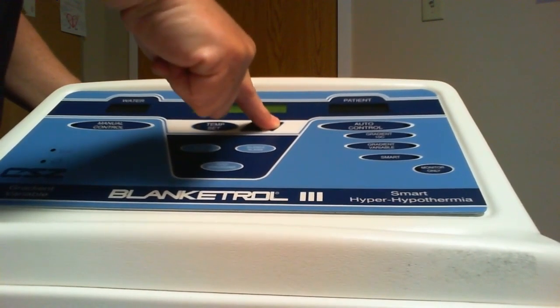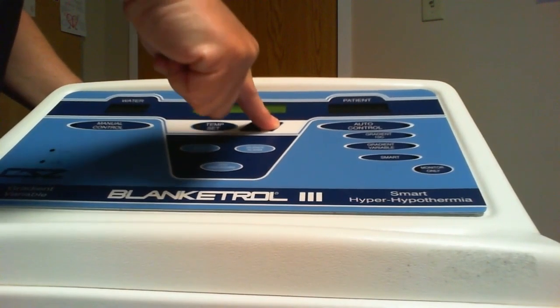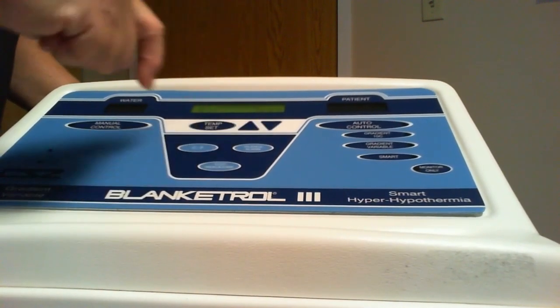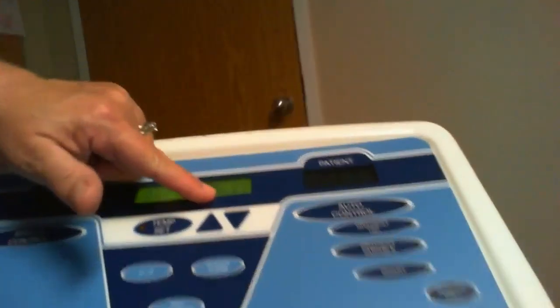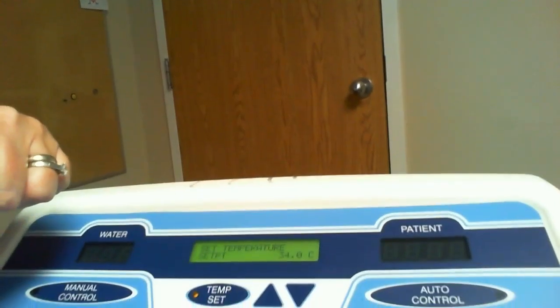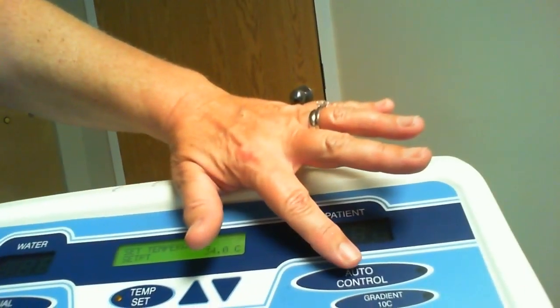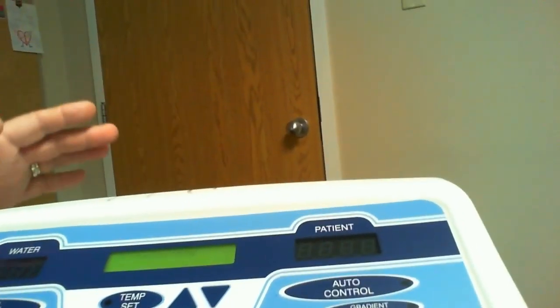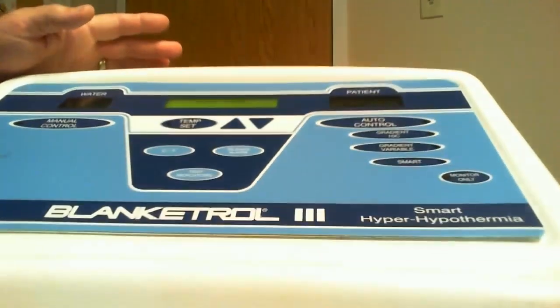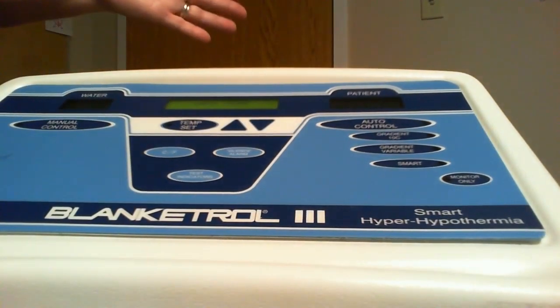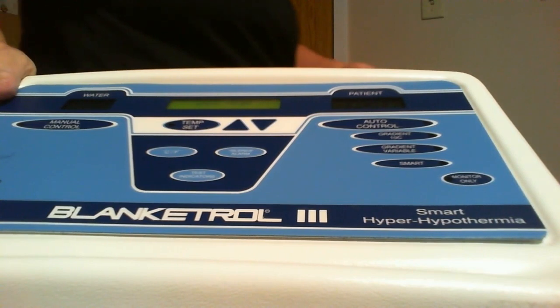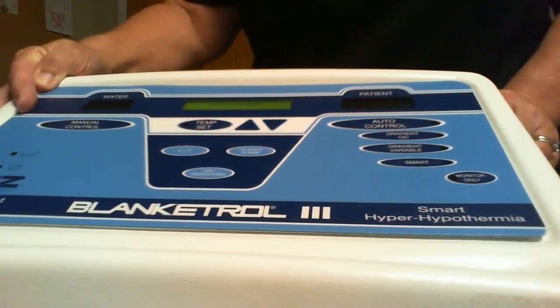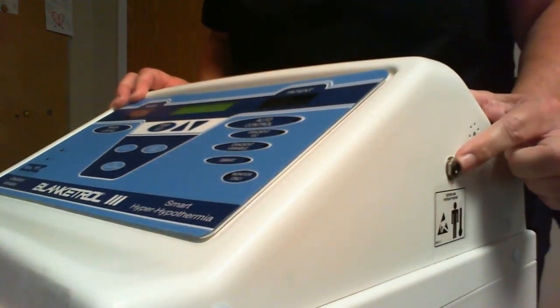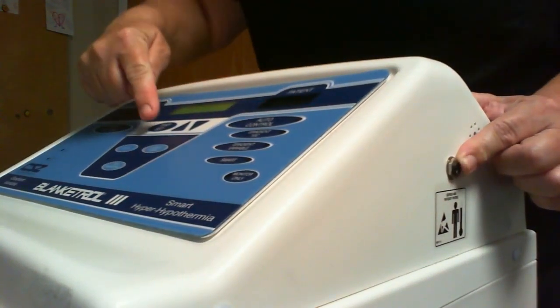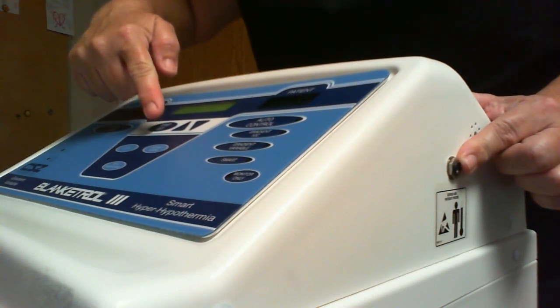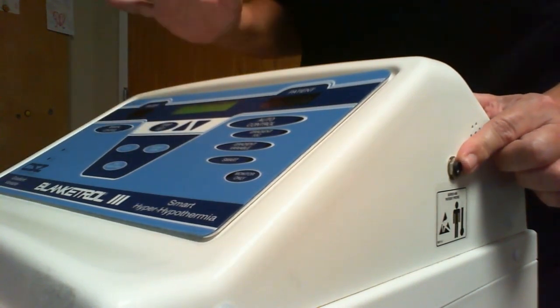So I want to cool my patient very quickly. And so I can push and hold, or I can continue to push. Now I'm set at 34 degrees. And I'm going to come over here and I'm going to push the auto control. And it is alarming right now that tells me check probe, because I do not have a temperature probe installed in the patient or the machine. So I am going to go back and hit temp set. That's kind of my home button.